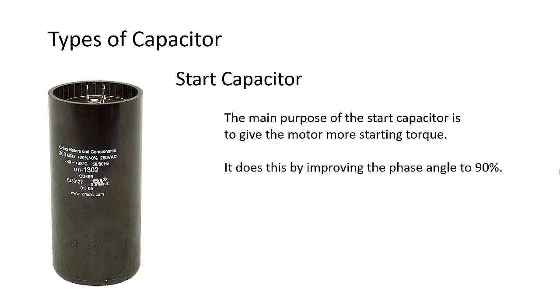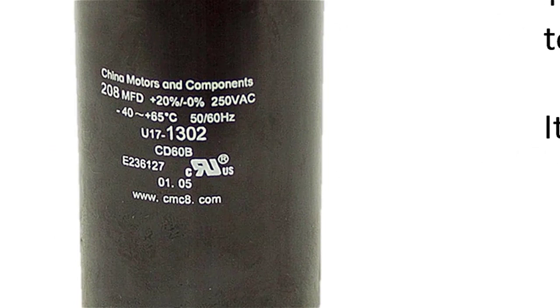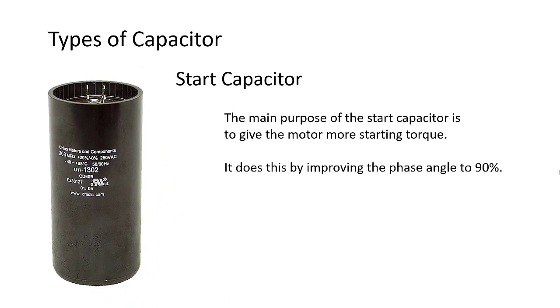Start capacitors are usually physically bigger than run capacitors. They also tend to be larger in capacitance values. Their capacitance rating comes in a range instead of a set number like in run capacitors. This is because the phase shift produced by an AC current through a start capacitor doesn't need to be as precise to get the motor turning.